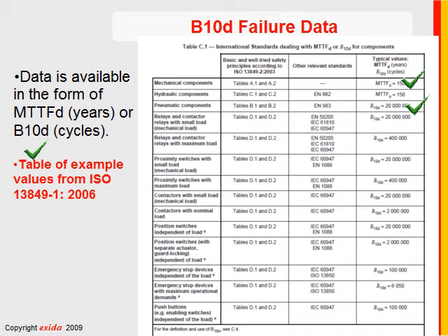And this kind of makes sense for machine safety. It really does. Because imagine a stamping machine or a press, and that machine is running ka-whump, ka-whump, ka-whump. Then it might be running a stamp every 10, 15 seconds. 4 cycles per minute. What's that? 240 cycles per hour. This machine could be moving pretty fast. The limiting factor is mechanical or electromechanical wear out.